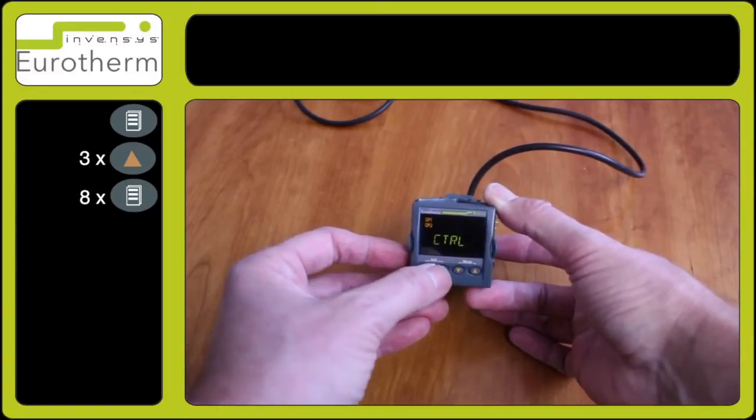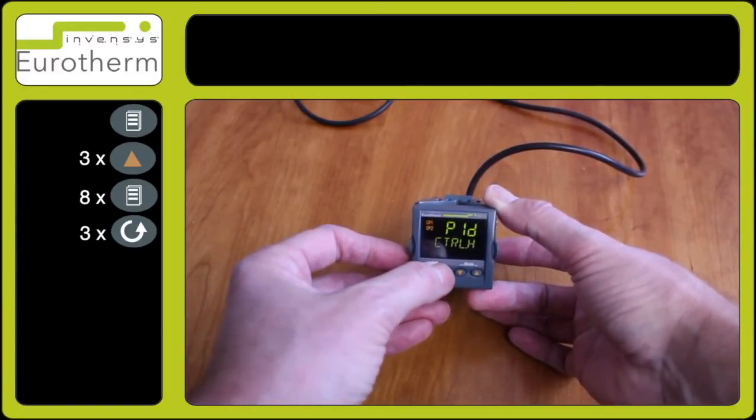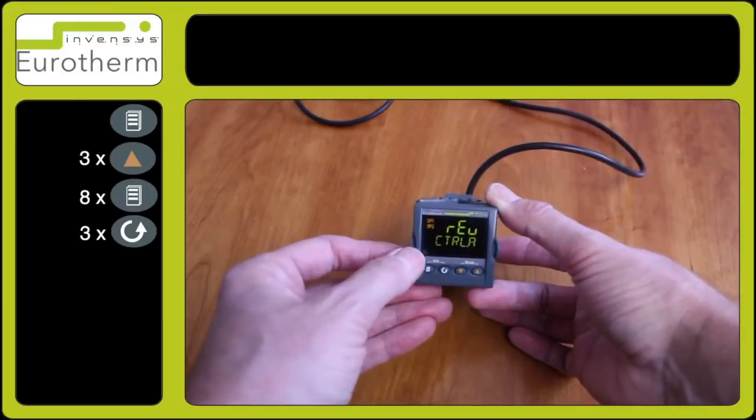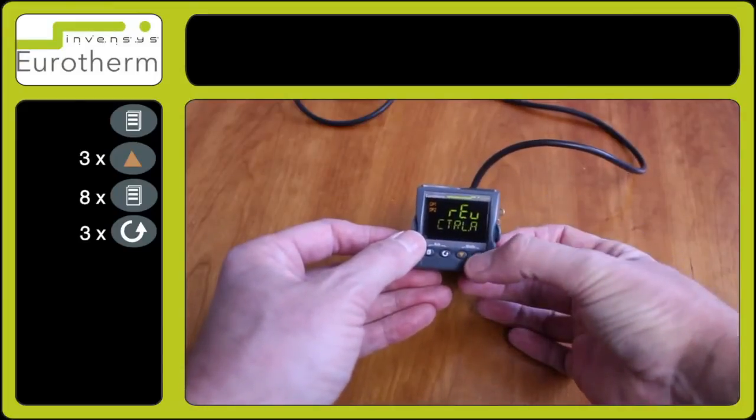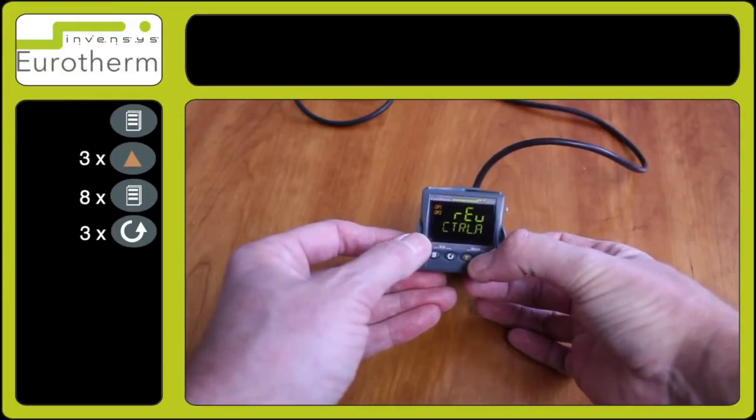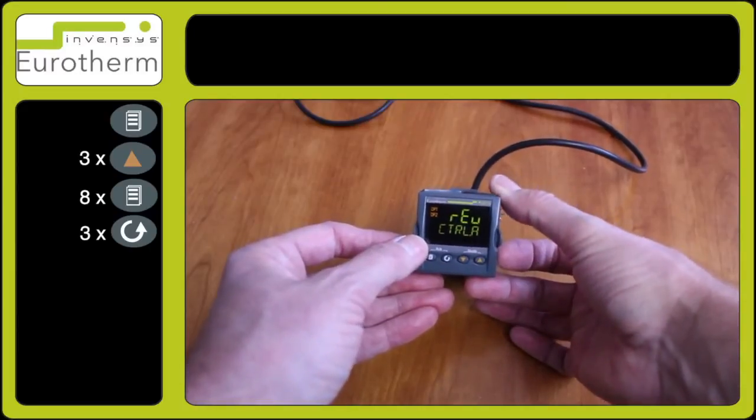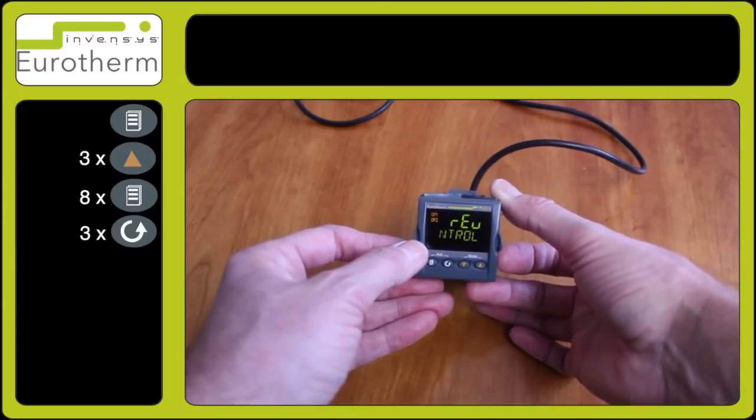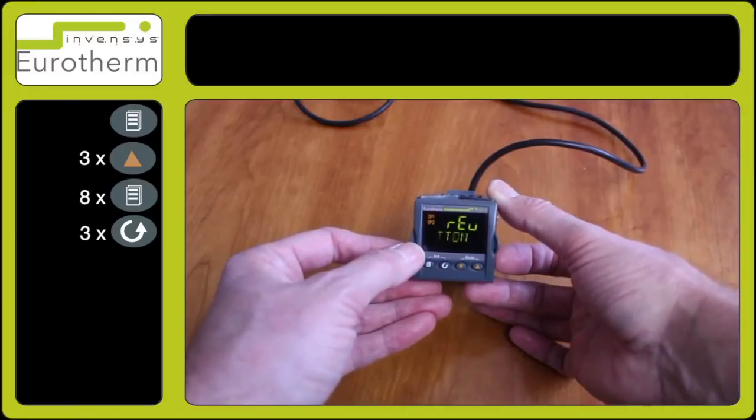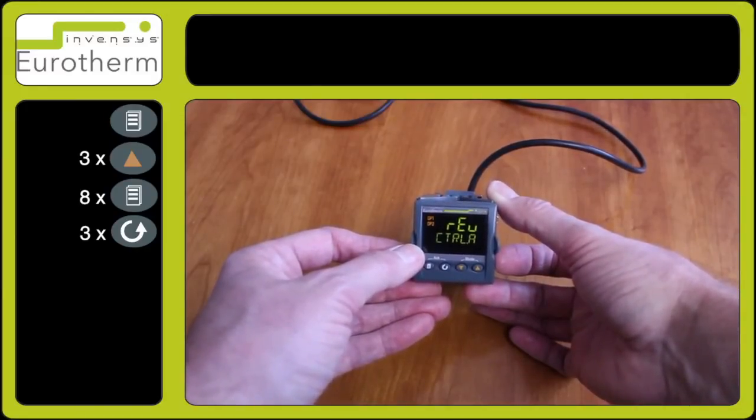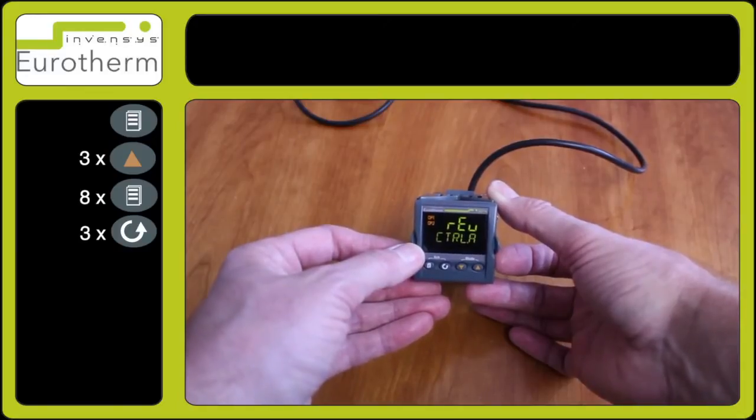Press the scroll key until CTRL.A appears. You can see in this particular case it is set to REU, which is a control action for the set point and the temperature. When the set point is above the temperature, this will activate the output.